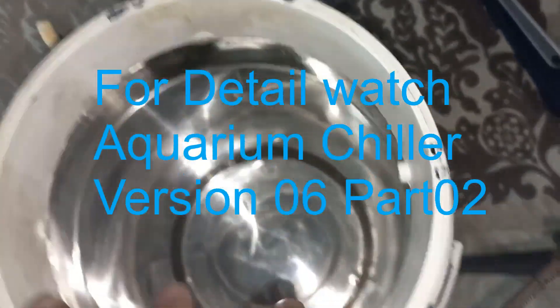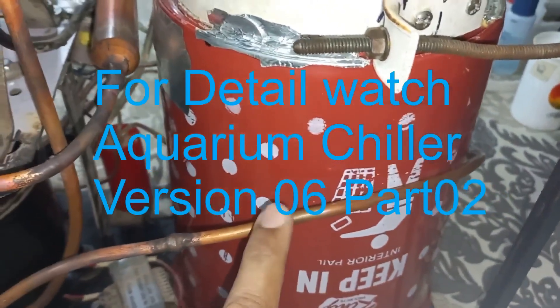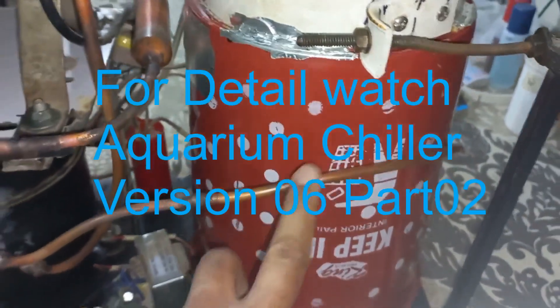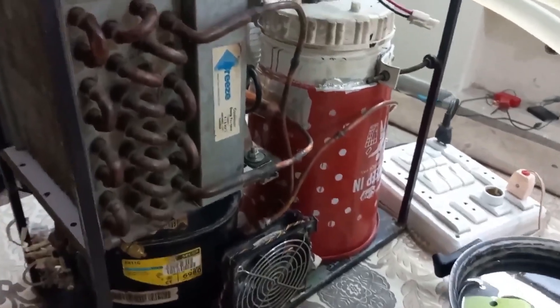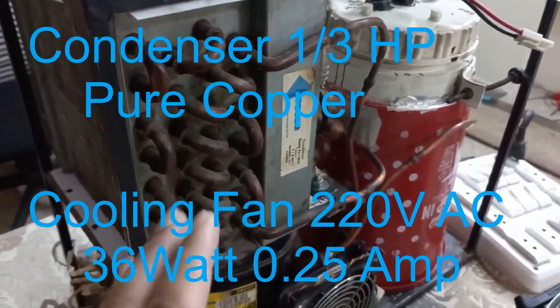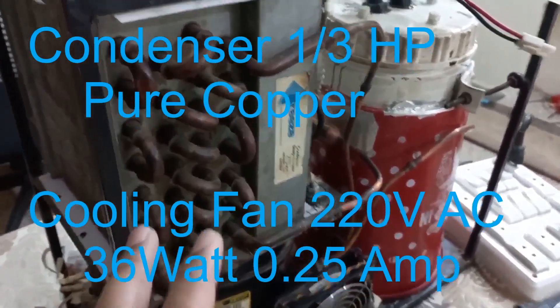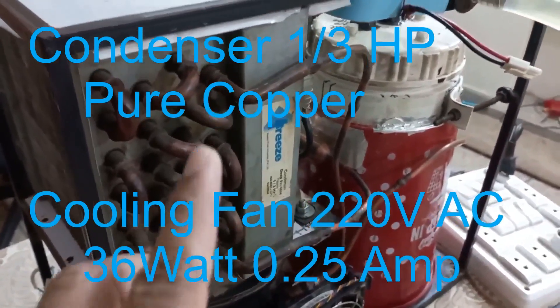I will not use this one anymore. The evaporator box is a stainless steel box inside, and outside is a round copper pipe, 1/4 inch diameter, 70 feet length. When I opened this I saw too much water inside the condenser. I have to clean this with CTC chemical because this is a copper pipe, so I can use CTC chemical on it.